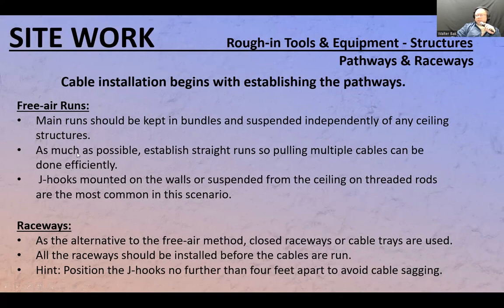When you run the wires, you're going to have what's called free air runs, or you're going to run cables in raceways. Some raceways, like a cable tray, just have cables laying on top, so it's sort of like a free air run when you consider certain aspects, like the type of insulation—the cable is still exposed. Doing J-hooks is considered completely free air. Free air means the cables are not enclosed in conduits, pipes, or wireways.